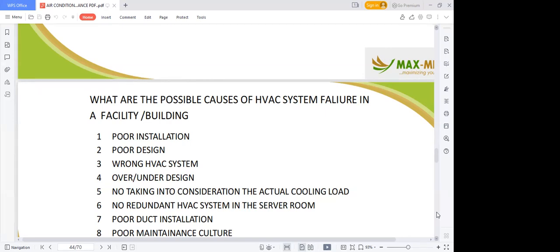If you know the area of your space to be 10 square meters, when you measure it, maybe it's about 5 by 2. So if it is 5 by 2, what you need to do is just 0.18 multiplied by 10. So what capacity would that give you? 1.8 kilowatts. So once I see a building, I can vary it. Like I said, it's a rule of thumb.